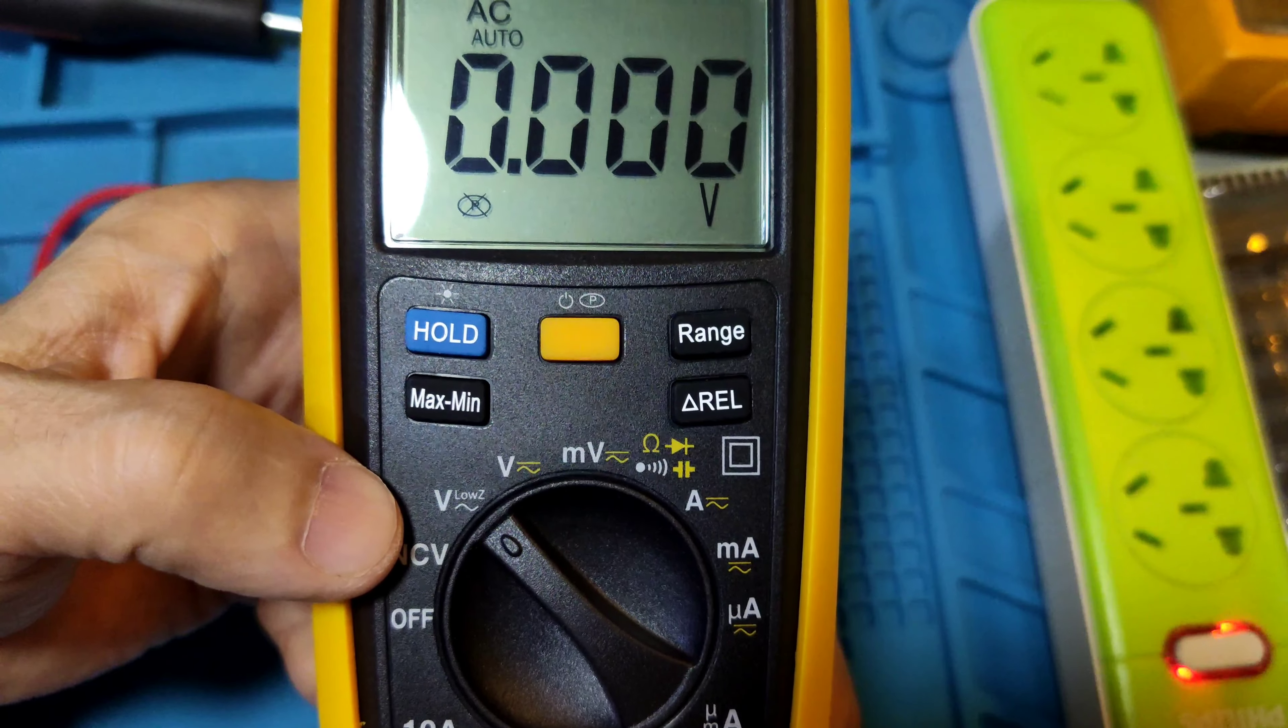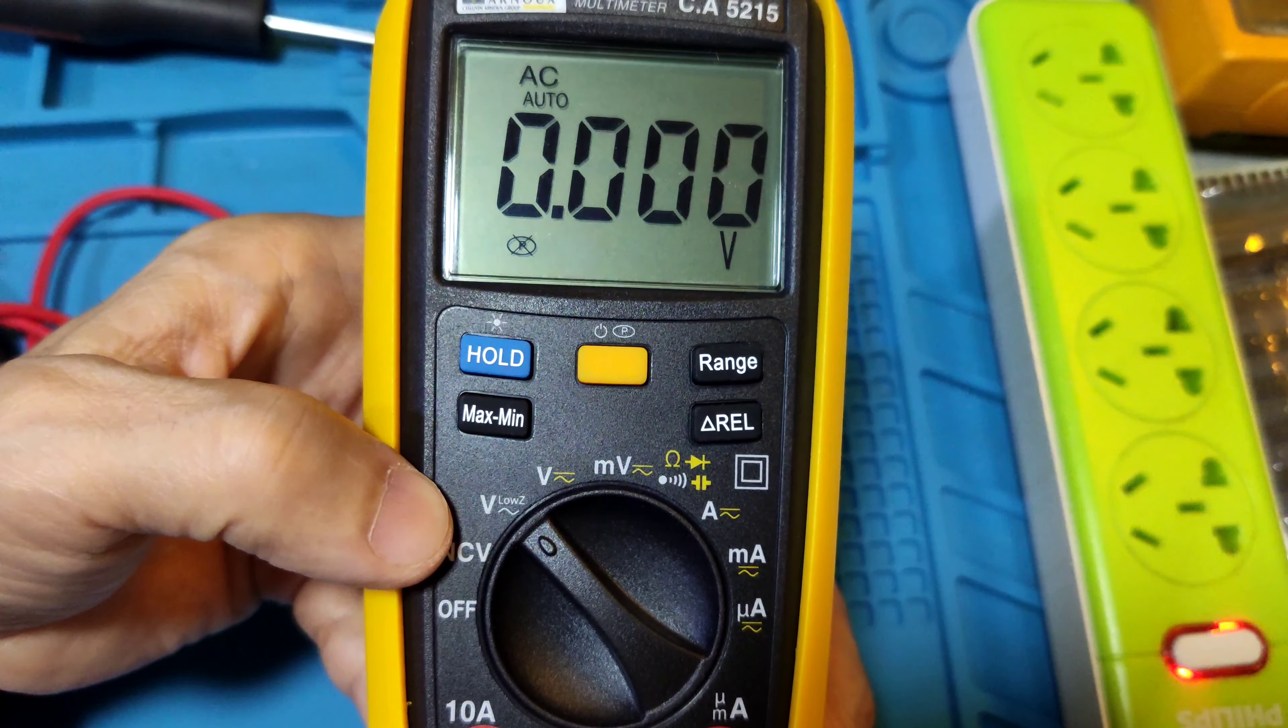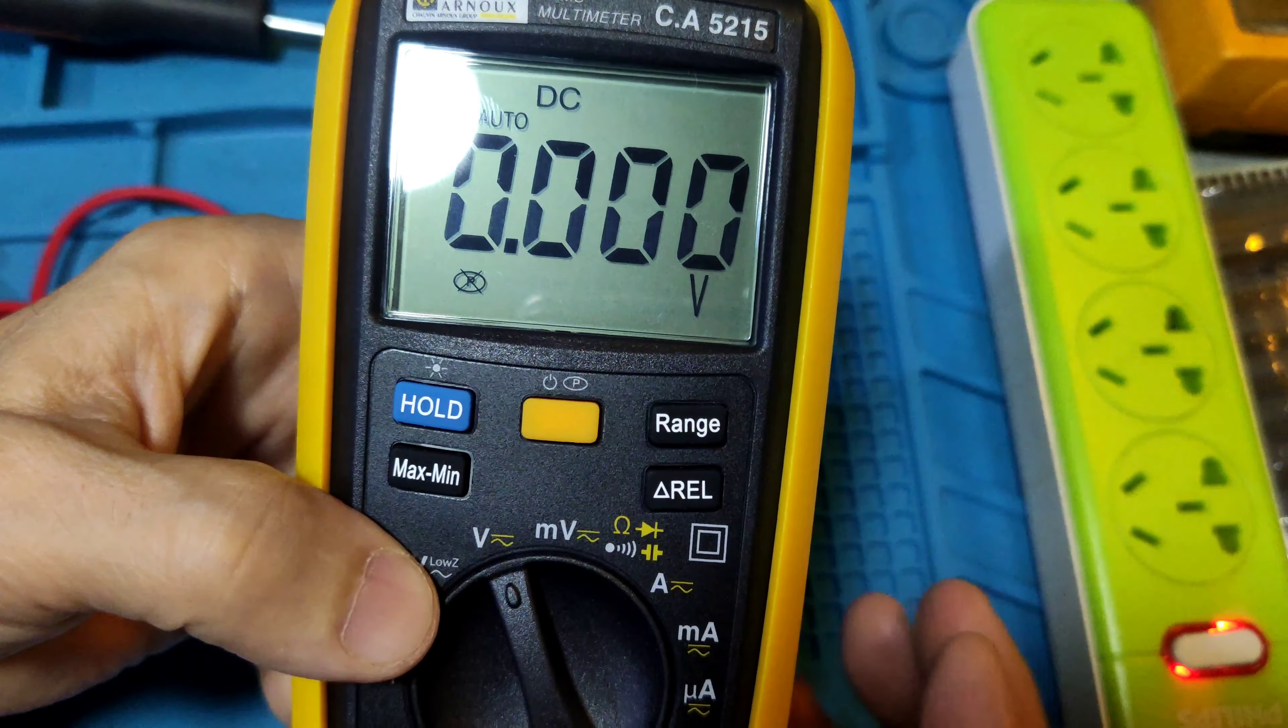Next is the low Z auto AC/DC range. In this position the meter can test circuit boards for ghost voltages - it can eliminate them. It can test the circuit board only, not for the electronic parts. Next is the normal voltage range. First one is AC, press the yellow key to turn to DC.